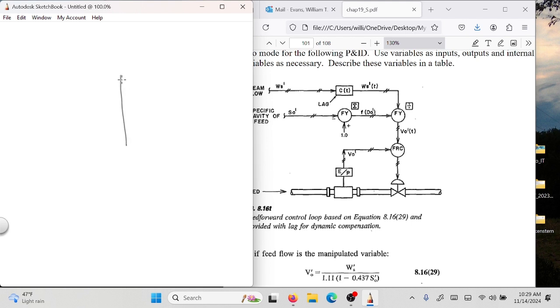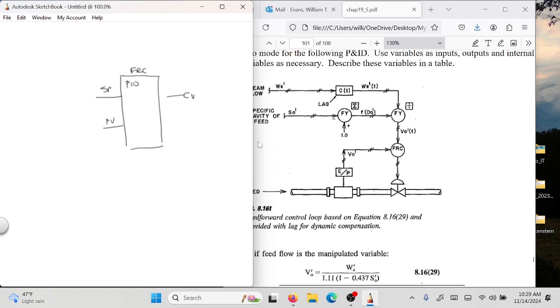So how do you program this cross-limiting diagram? There's one PID controller — the FRC. The rules: there's a SP, a PV, and a CV or output. The CV goes to the valve — that's easy. The PV is the flow signal. Where's the set point? The set point is this calculated value — VO prime. It's a mathematical equation: this equation right here came from this combination of factors, and it's feed forward loop control with lag for dynamic compensation.